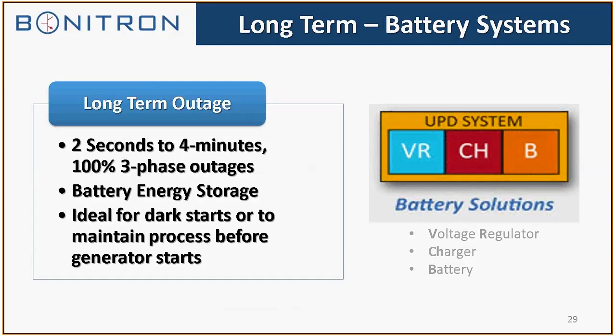Usually when we specify a long-term outage, we're looking at the specification of utility power out, or AC line voltage out, to gen set up. That can be anywhere from, depending on the type of generator, 5 seconds, and I've had specs that were up to 30 seconds because they wanted several restarts capability of the generator. So they want the ride-through to back up that time so there's no bump or drop of the process between utility power out and gen set up. So we run into that spec.